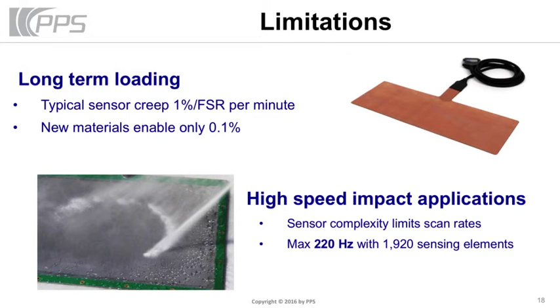There are limitations. I'm not trying to just pitch our technology as the best. The worst thing in terms of sensor performance, compared to load cell and MEMS type sensors, we really fall short on creep. Typical sensors we have are about 1% full scale range creep over 1 minute. We have developed and demonstrated sensors with 0.1%.